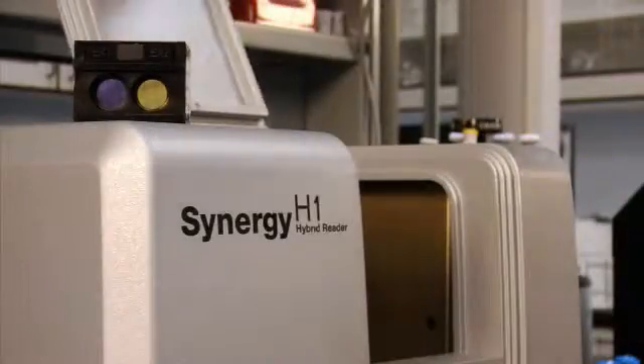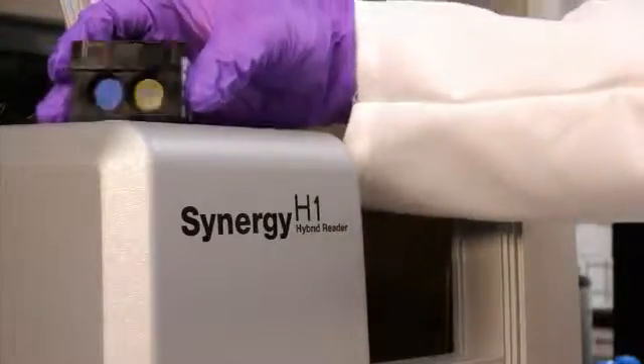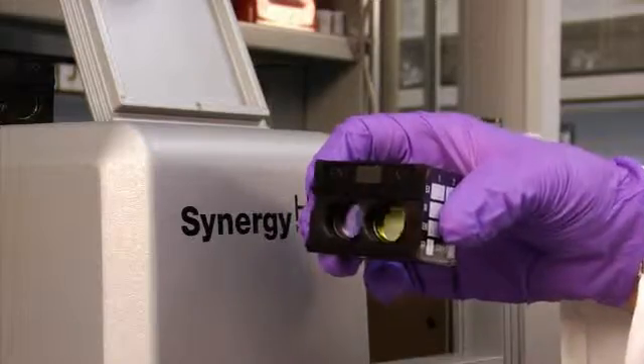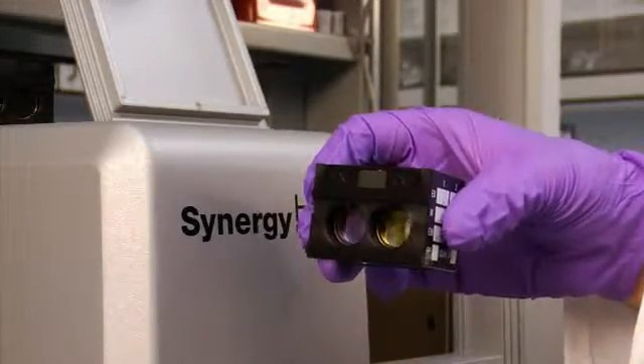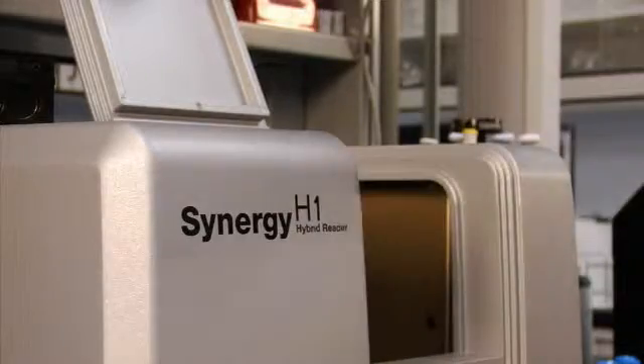The filter optics come with easy-to-use filter cubes. Each filter cube contains all the required filters and mirrors to detect specific fluorophores. The cubes are positioned using magnets and can be swapped in a matter of seconds to easily switch from one detection mode to the next.